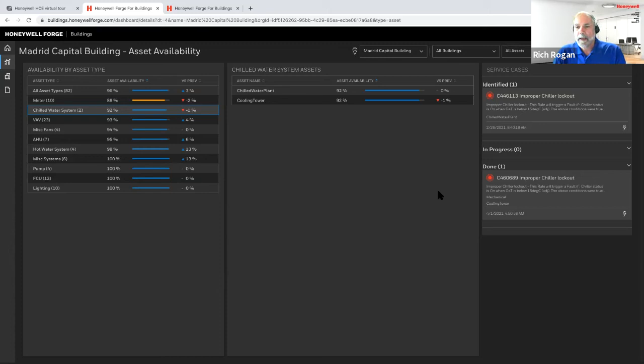Having touched a little bit on the predictive maintenance capabilities, I'm going to go back up and talk about the first of our machine learning solutions, which is energy optimization. Energy optimization is a closed loop machine learning solution which essentially creates a model of the HVAC assets, the chillers and boilers, the air handling units they feed, as well as the zones or variable volume boxes that they may feed. What it does is calculate the optimum set points for some very specific control algorithms within the building.